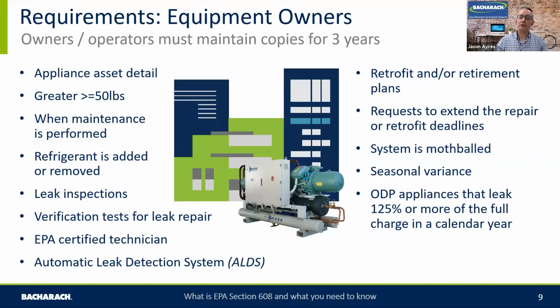The leak inspections, and we'll come on to that in the next couple of slides. These are checks that you have to do on the system. If you've breached a certain leak rate, you have to capture that and have that available as well. EPA's fundamental underpinning is about refrigerant management, containing leaks and reducing leaks. So if you do have a leak, you have to do verification checks afterwards, an initial and a follow-up verification. Again, as part of that process, you need to capture that information and have that available.